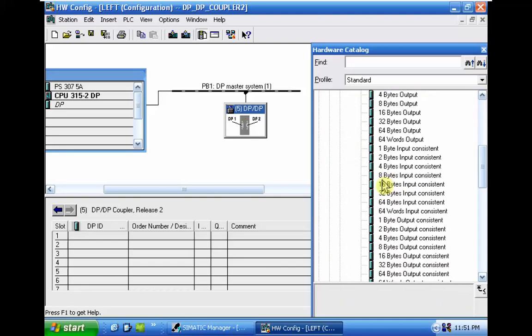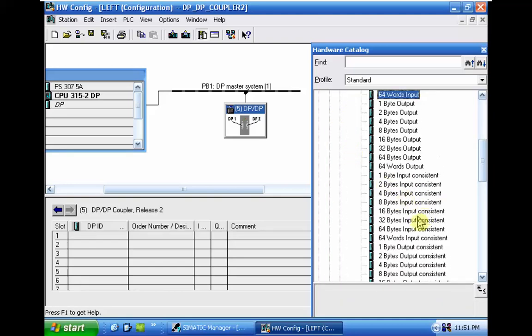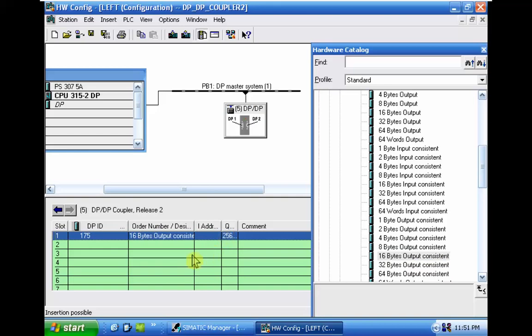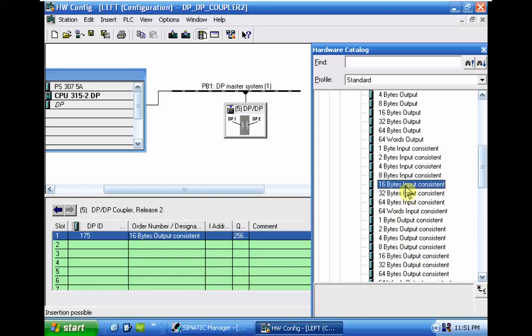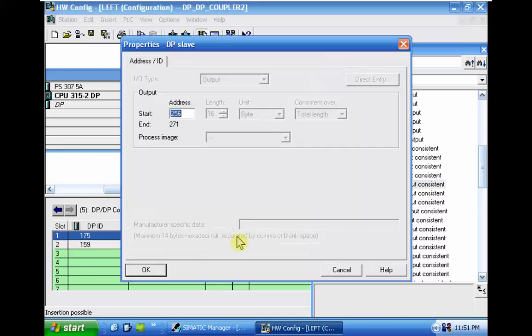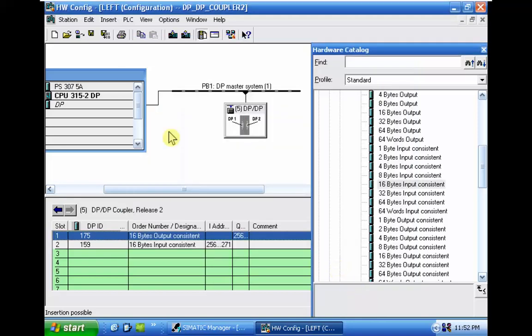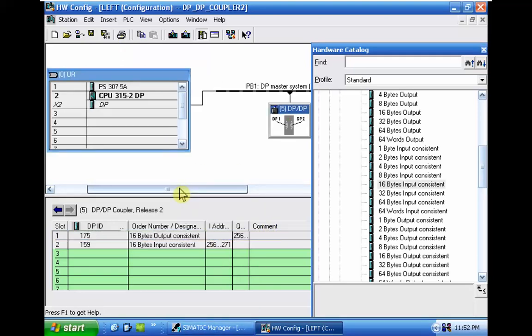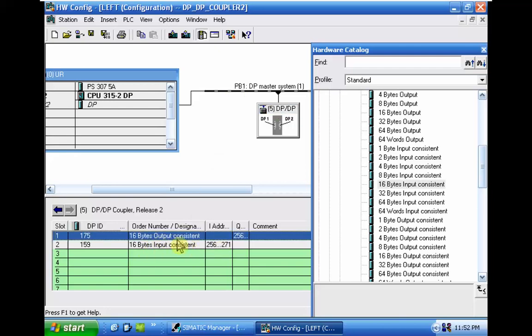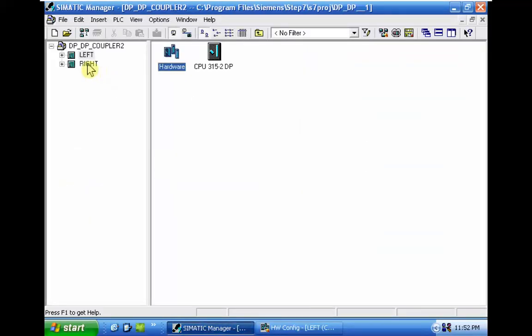And this type of data, they are consistent. We want to transfer 16 bytes of consistent data, and we will receive 16 bytes of consistent input signal. So we send data, receive data, they are consistent. If you check the properties they are consistent over total length. For the next CPU, this is the CPU Profibus 1. For the next CPU, first we should receive this type of data and then send. The order should be reversed.